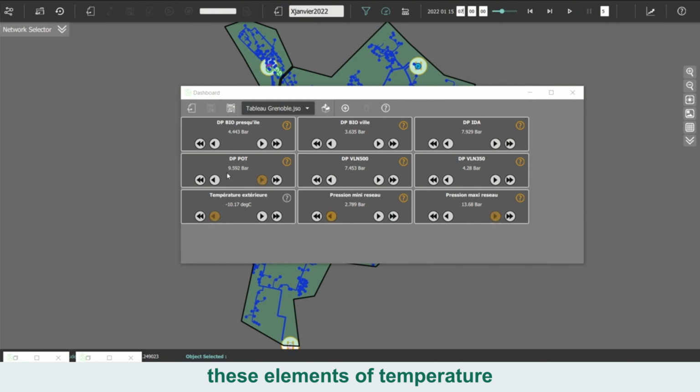When combined, these elements of temperature margin at the level of a single consumer, temperature margins at the level of all consumers, and satisfactory overall hydraulic conditions demonstrate a significant potential for lowering the temperature of this network. To sum up, this video illustrates how District Lab H Simulation Studio software can be used to analyze and optimize the operation of a district heating network.